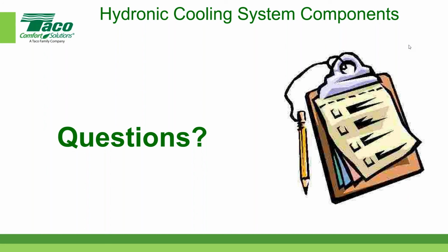I guess it's important to realize that there's a lot of similarities between a heating system and a cooling system, but from a design standpoint, there's probably a lot of differences too. You have to take so many different things into account, right? Yeah, one of the major considerations for a hydronic cooling system is that it has to be properly insulated so that the piping, the components, the valves, the pumps, all those things don't sweat all over the place. There was a problem in a building that I had to look at about 4 years ago. And it was a fan coil system inside the building.